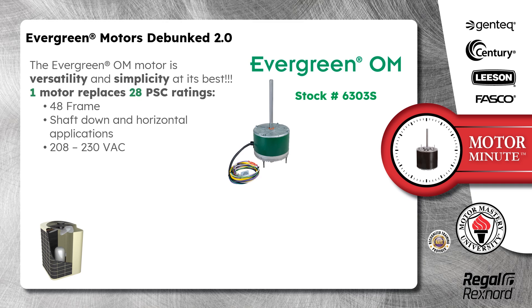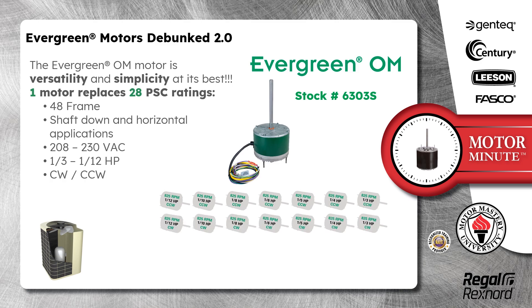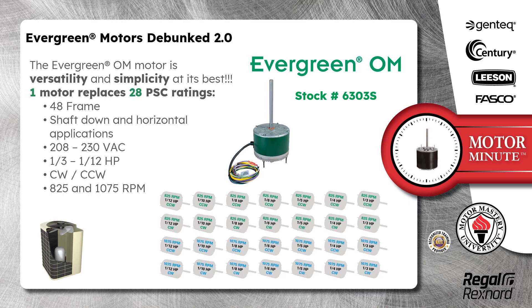One motor replaces 28 PSC ratings including 48 frame, shaft down and horizontal applications, 208/230 volts AC, 1/3 to 1/12 horsepower, clockwise and counterclockwise, 825 and 1075 RPM.